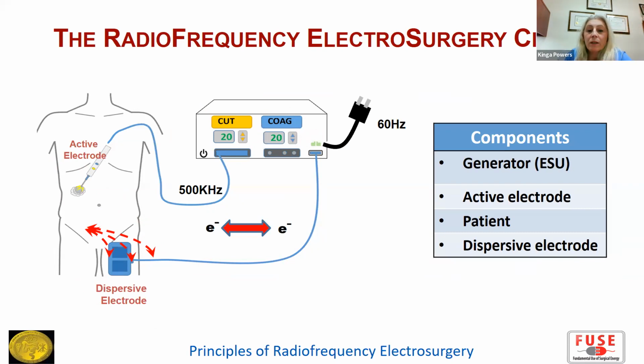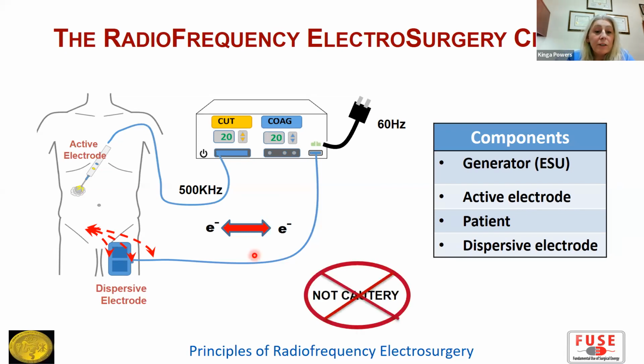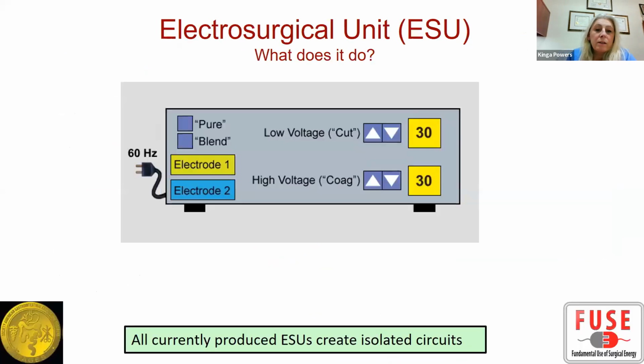The historically used grounded circuits increase the risk for current diversions through contact with conductive elements like EKG wires, or causing burns through metallic elements on the OR table. So those haven't been used in over 40 years. So we're using a dispersive electrode, not the grounding path. And this is definitely not cautery because there's a current. So the ESU does three things. I already showed you how it converts the low frequency wall output to the high RF frequency of 500,000 hertz.